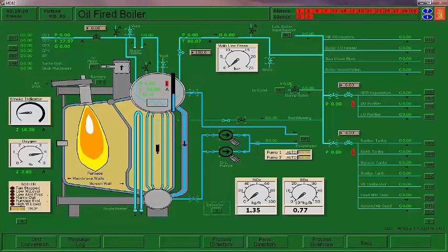Okay, and then on the boiler, this temperature, you have to be above 100 C. So, you know, this was 30 minutes. This would start probably producing steam about 40, 45 minutes. And in real life, as soon as I saw any steam coming out of the vent, if it hasn't been an hour, you shut the fire off. You wait until the hour time period is up, and then you light off again.